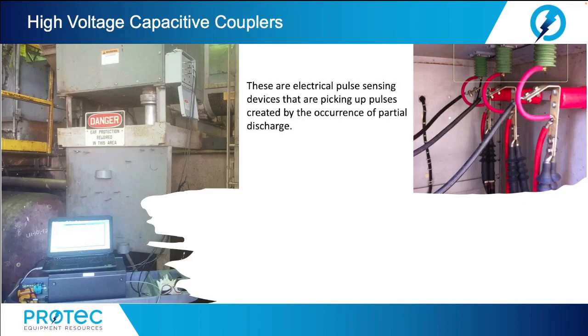And now let's take a look at high voltage capacitive couplers. These devices are typically installed when the equipment is de-energized and then can be used for online monitoring and testing of partial discharges. These are electrical pulse sensing devices that are picking up pulses created by the occurrence of partial discharge.